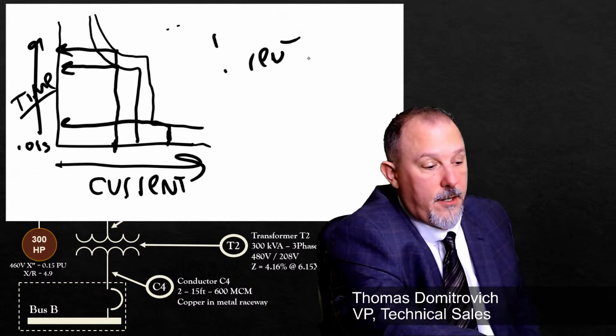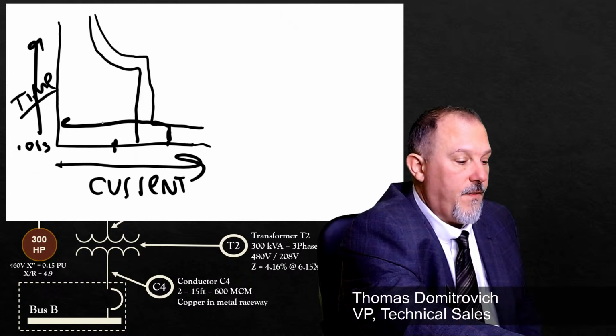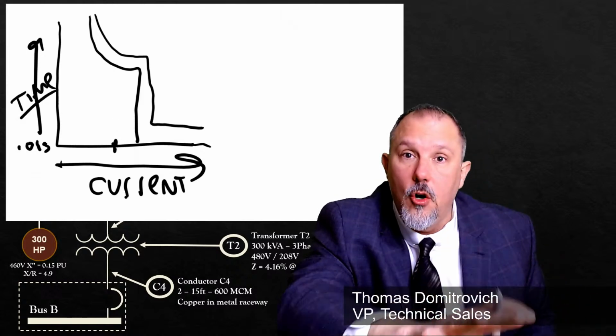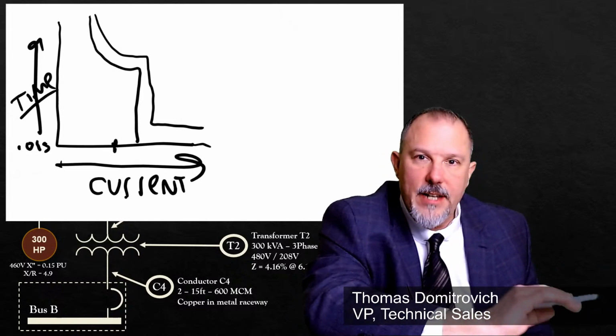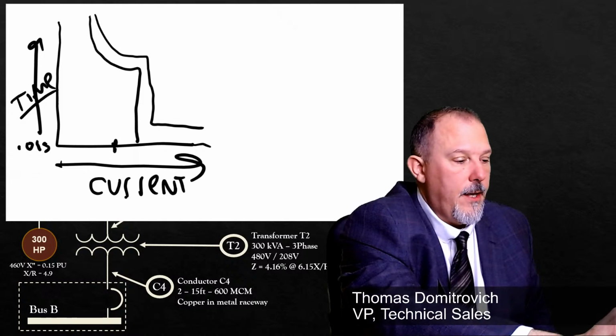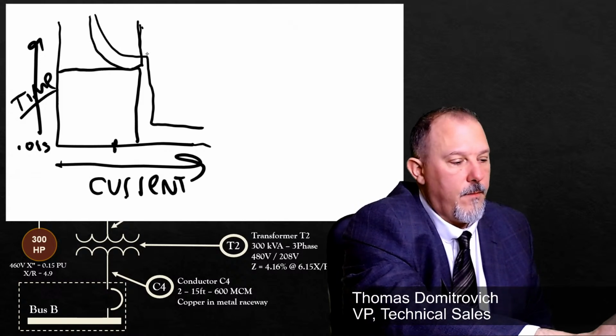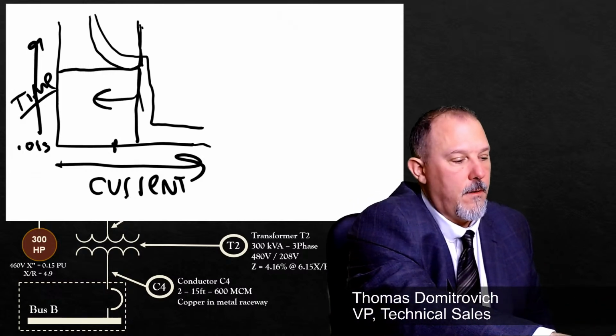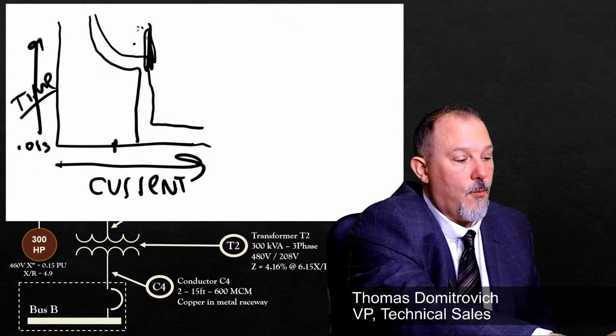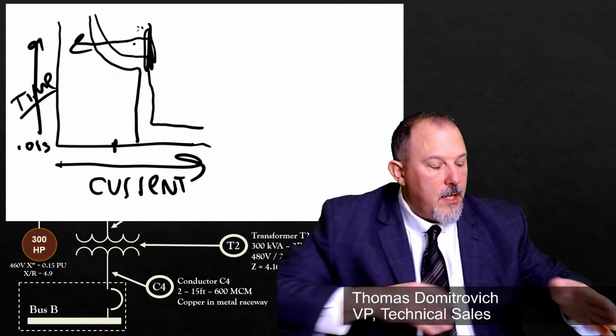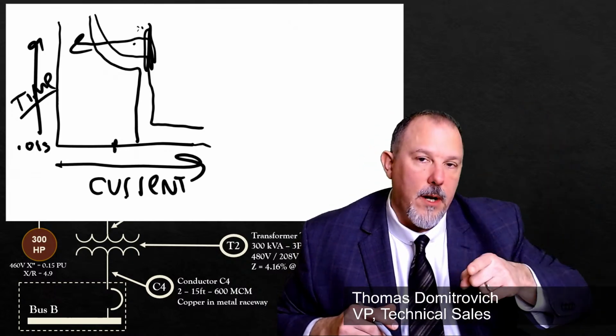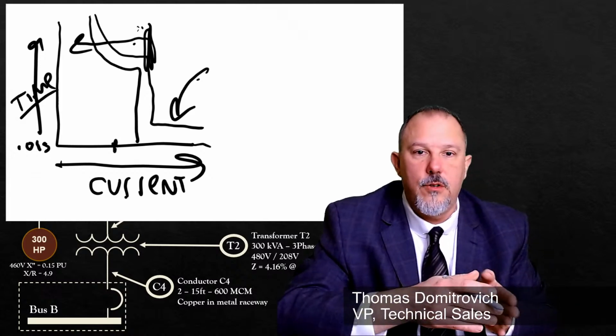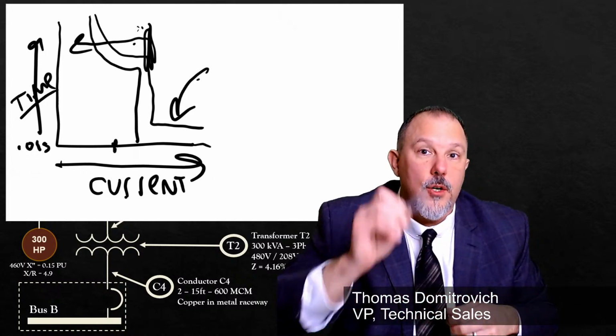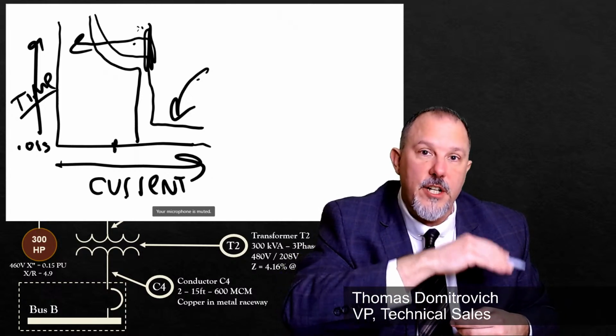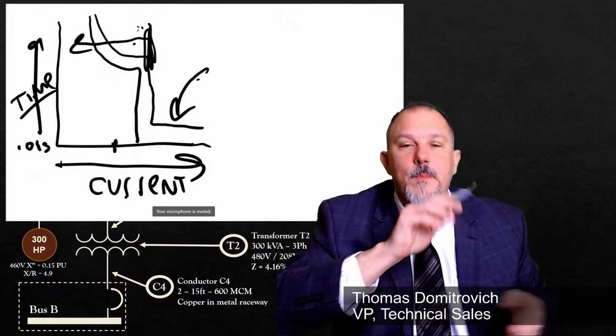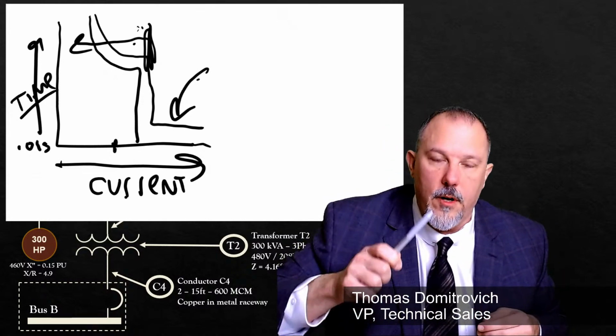All right, so this is what we call the time current characteristic curve, and how we started going down this road, if you would recall, is I was talking about the overload to short circuit. On a time current characteristic curve for a circuit breaker or a fuse or whatnot, this area of the curve, I'd say from about right here where that picks up down, you're in the overload region, because you're in a long clearing time of this circuit breaker. When you get into this region, you're into higher fault currents, which are more than likely going to be a short circuit current. But don't get me wrong, just because you're in the instantaneous region of this circuit breaker doesn't mean it's a short circuit.